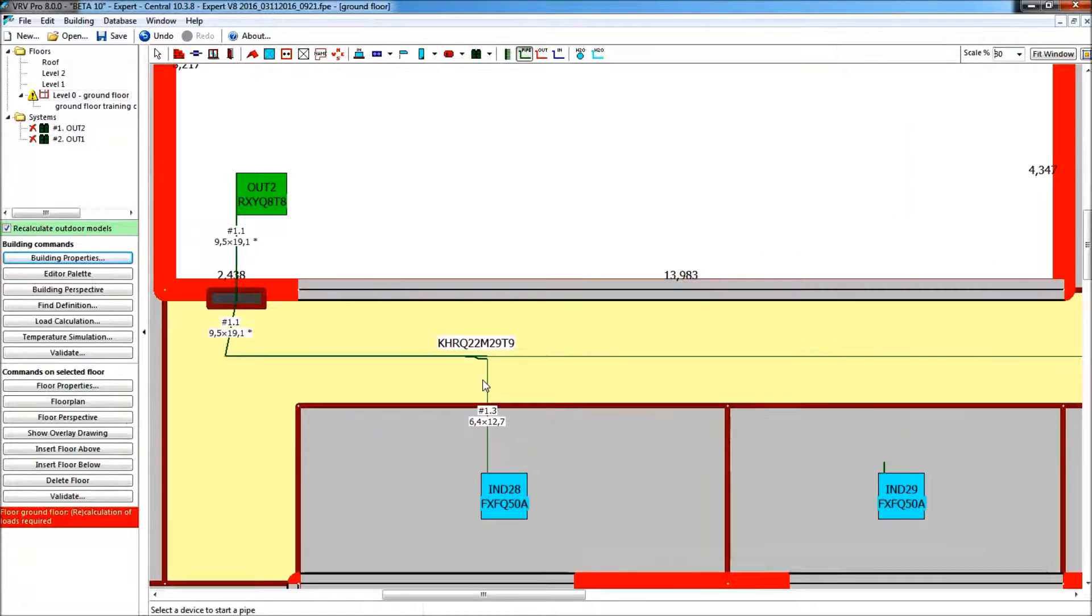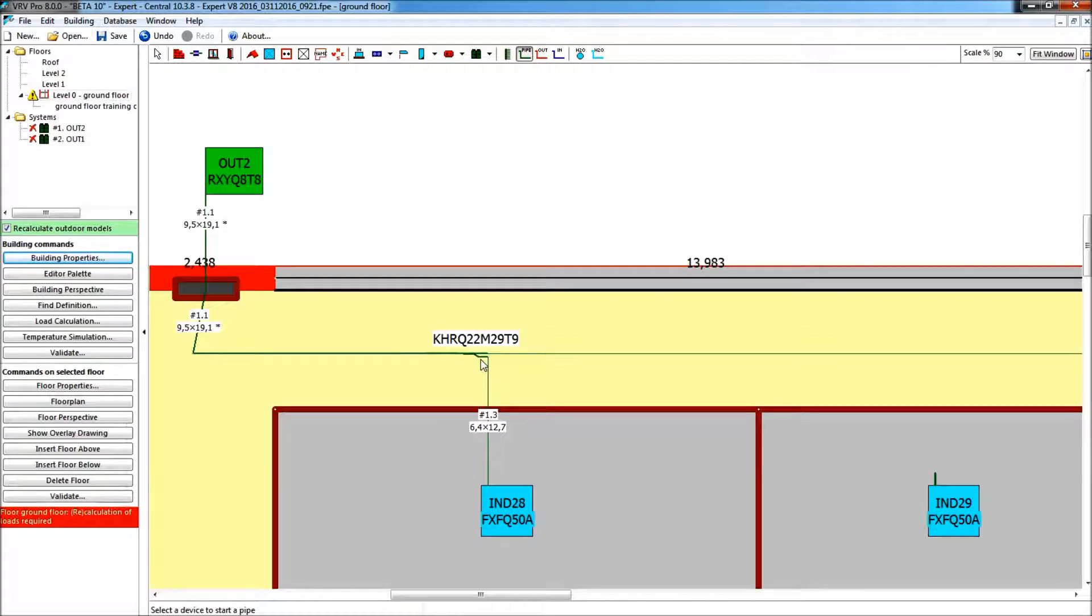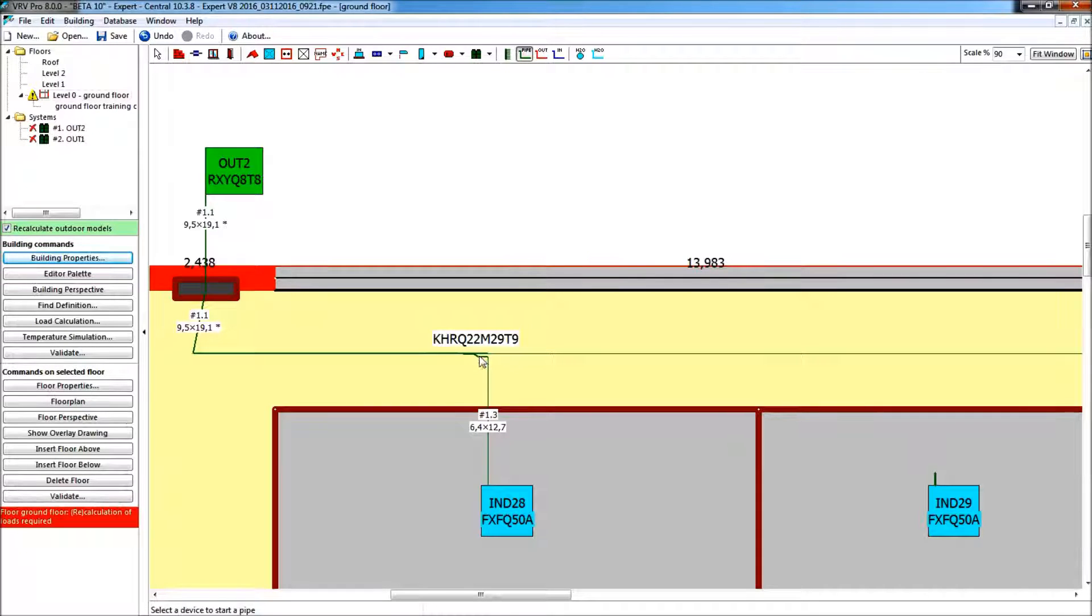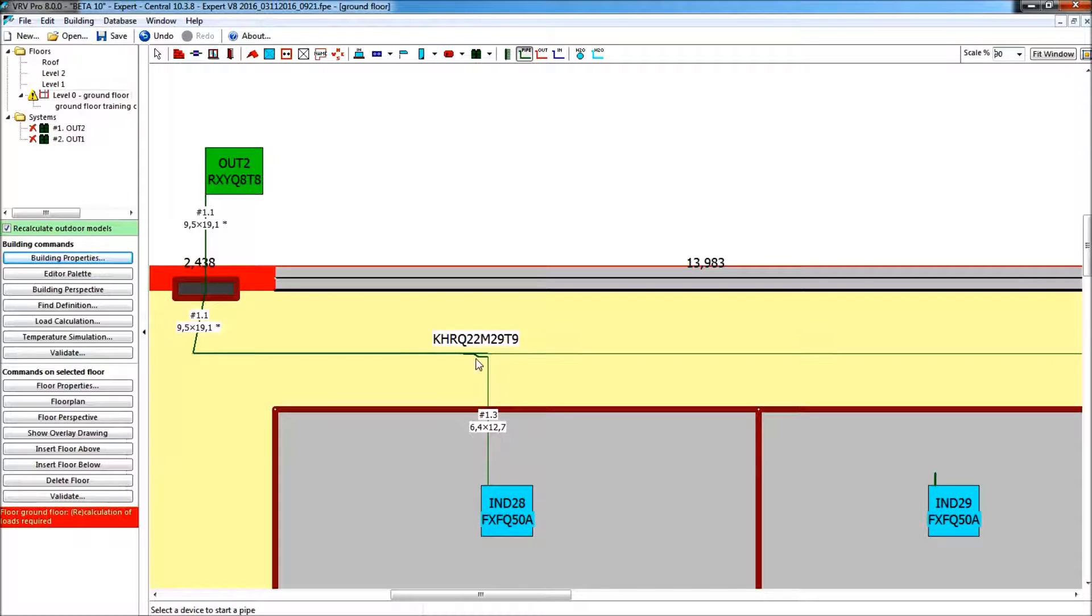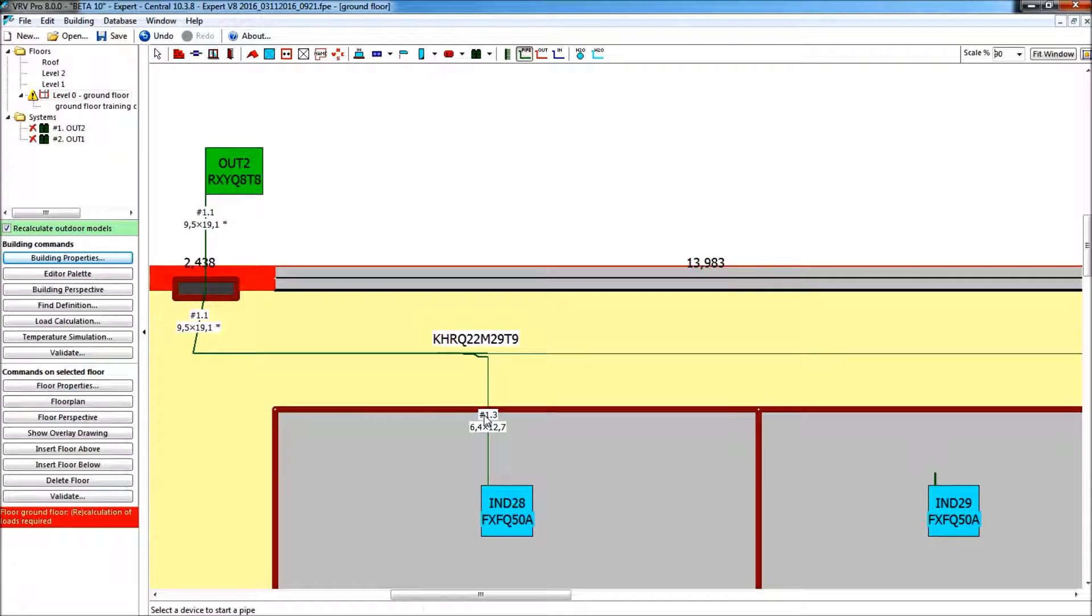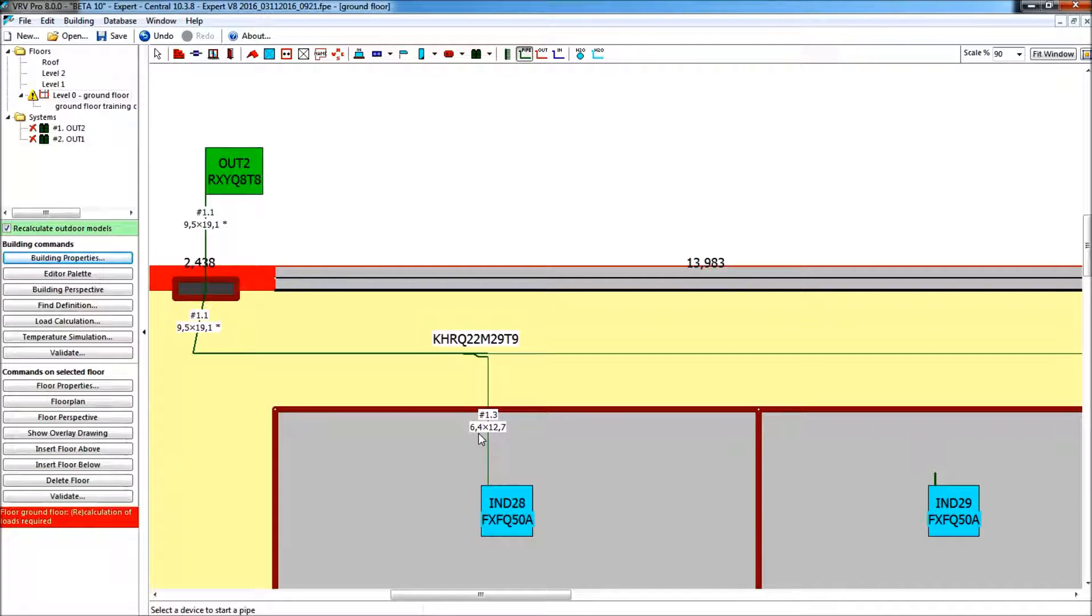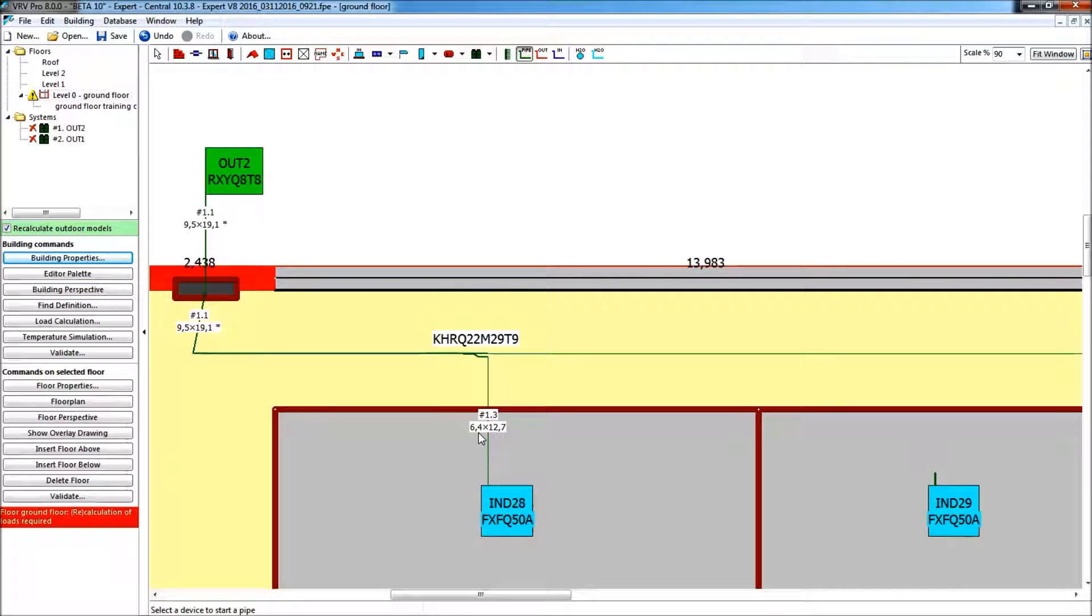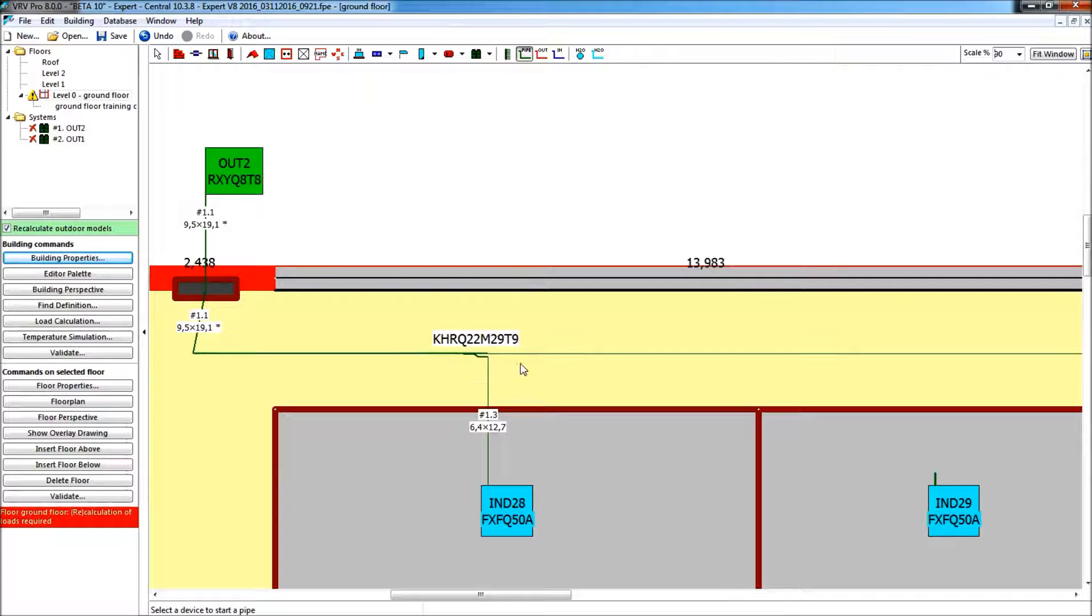You can see that right away the diameters of the joints are selected and that at the same time, with the diameters, I get something new here, which is the pipe numbering. By the way, joints are drawn in this way now. So the pipe numbering, I see that this would be pipe number 3, that belongs to system 1, and it has one 1/4 inch and one 1/2 inch, or 6.4 and 12.7 liquid and gas pipe. So this is also something new.